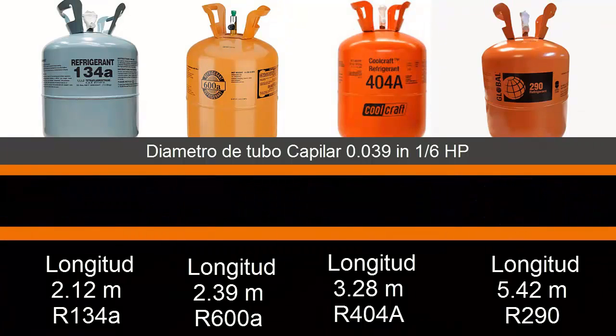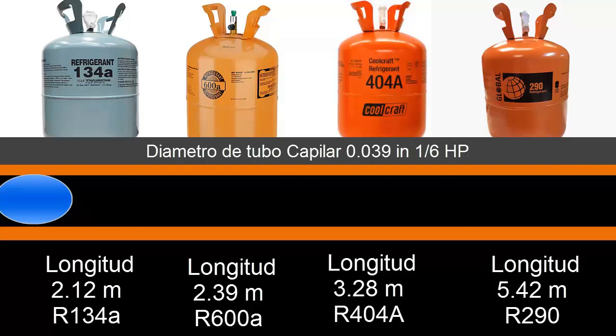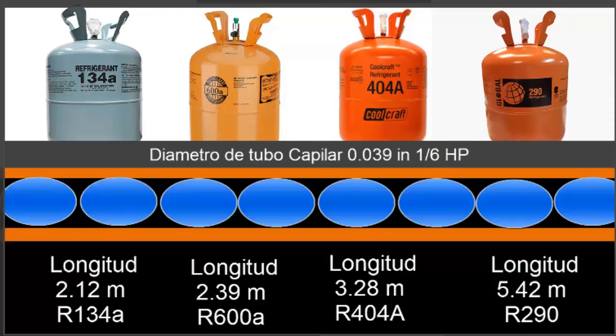Observe how for the same diameter, when we use different refrigerants the length of the capillary must logically change. Let's see how R-134A has in all cases the smallest length, followed by R-600A, followed by R-404A, reaching R-290 which is the one that has the longest length.